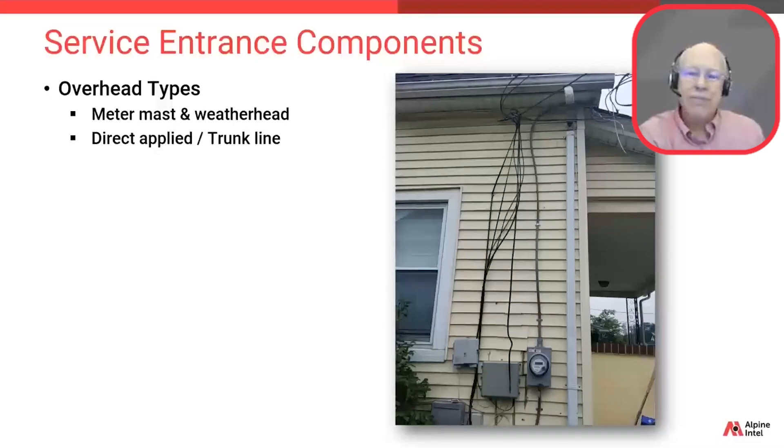Let's talk about another type of overhead service entrance. This type is referred to as direct applied or trunk line, also often referred to as a service entrance or SE cable. In this case, conduit is not needed as that cable sheathing is watertight — it's attached directly to the siding of the home. These direct-applied applications do not go above the roof line, because there's nothing to hold them up there. They can only reach as high as the highest point on the building.